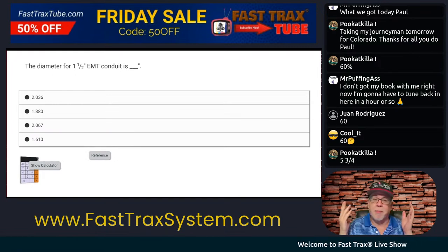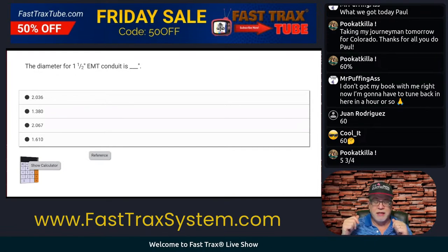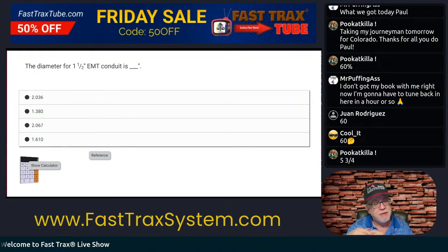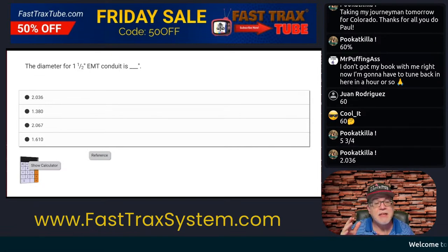Tonight, we're trying to do things to commit to memory. If I need to find something about the raceway and the size, it's Chapter 9, Table 4. If I need to do raceway fill where the conductors go in the raceway, it's Chapter 9, Table 5. If I need to know the properties of a conductor like the circular mils, and it's smaller than 250 kcm, then it's Chapter 9, Table 8.